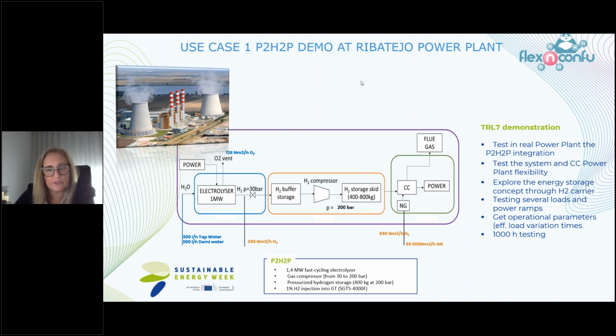The demo plant will be used to test the concept in a real combined cycle power plant, explore the energy storage concept through hydrogen as a carrier, evaluate gas turbine compatibility with other fuels, test several loads and power ramps to characterize the power to hydrogen to power plant limits, and obtain operational parameters like efficiency and load variation, extrapolating results for higher H2 percentage injection. The goal is to operate the demonstrator for 1,000 hours connected with the combined cycle.